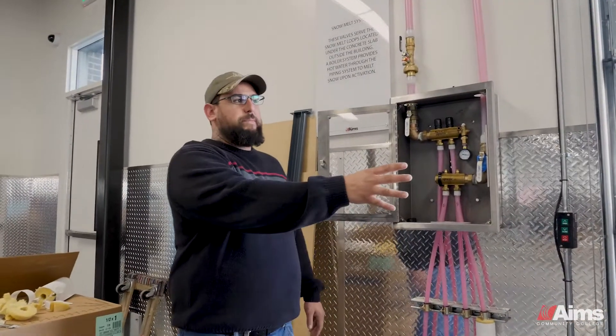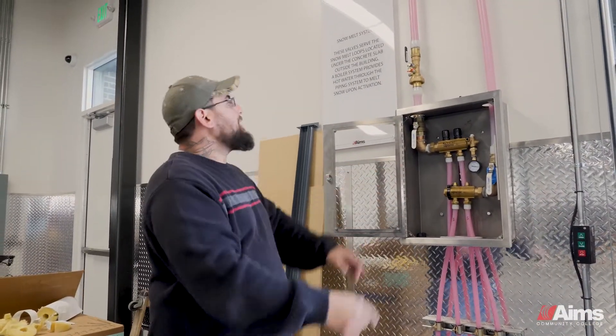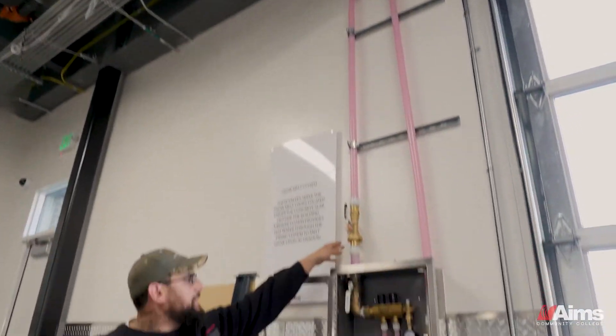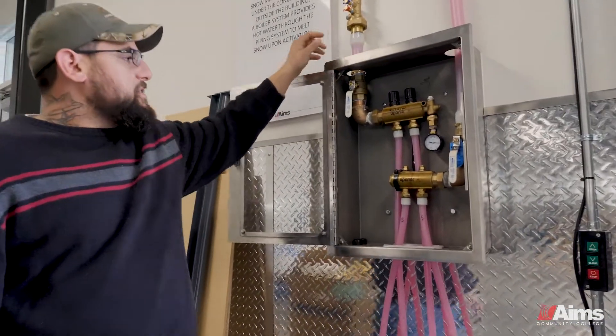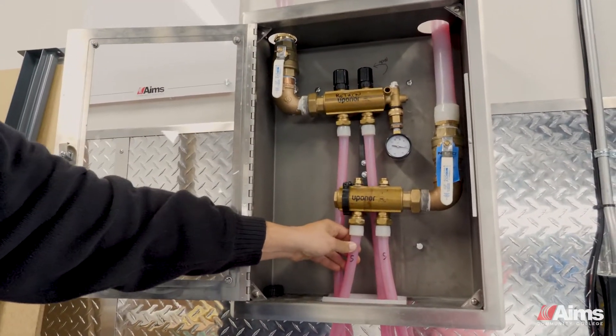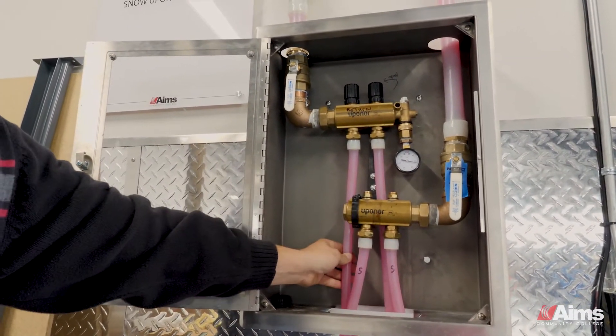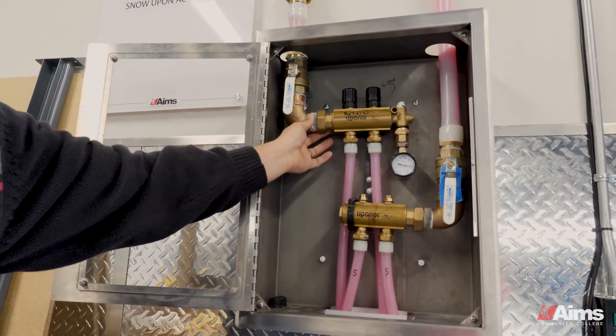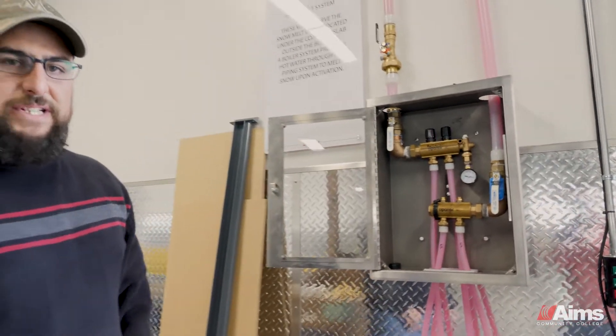After it's pumped from the heat exchanger on that side, it comes through over the roof and into this box here. This gear we have is a manifold. The fluid comes in through this pipe and is split to run out to the slab outside, then returns back through it and back to the heat exchanger to receive more heat for additional snow melting capabilities.